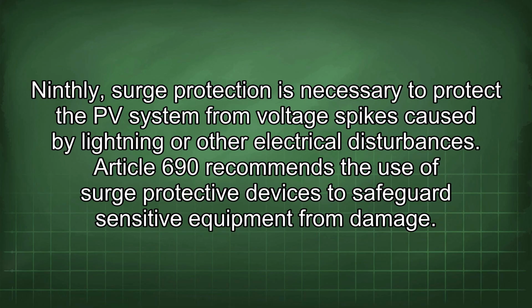Ninthly, surge protection is necessary to protect the PV system from voltage spikes caused by lightning or other electrical disturbances. Article 690 recommends the use of surge protective devices to safeguard sensitive equipment from damage.